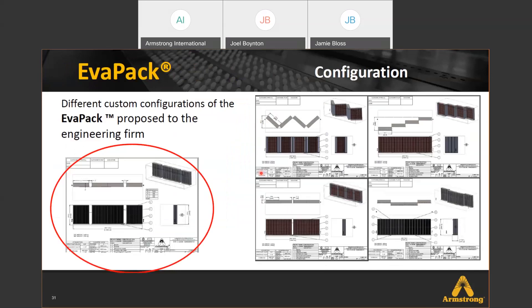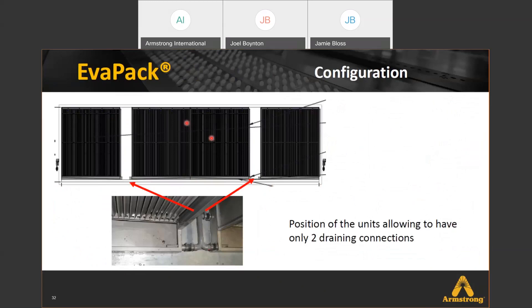Here are examples of the different configurations we initially proposed to the data center — a couple of staggered or V formations, as well as some offset formations. But this straight-line formation is the one they chose to go with. The reason they chose this configuration is that they were very interested in reducing the number of drain valves to as few as possible, and they were able to achieve this with only two drains for all four cassettes — two cassettes butted up next to each other and two on the sides with space in between for draining, as depicted here.